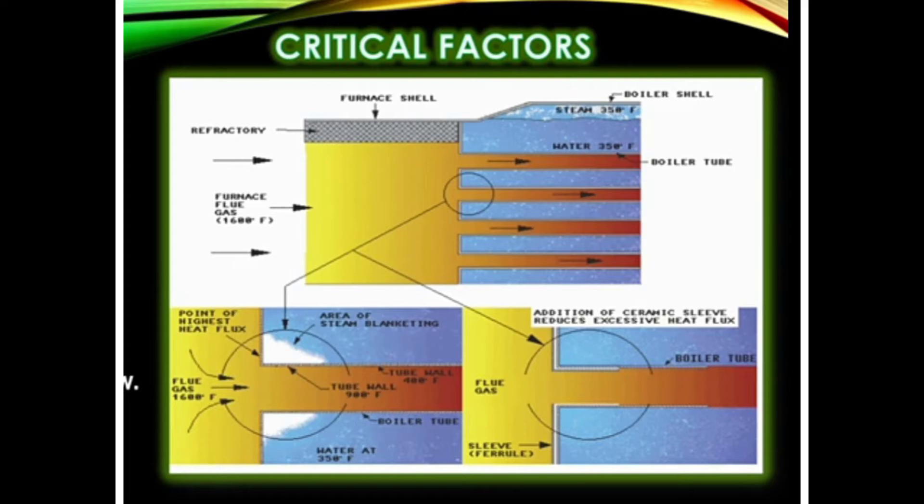At these corners or edges where flue gases first enter, there is very high heat flux and temperatures reach 900 Fahrenheit. Due to this high temperature, steam pockets are created at the corners, which is called steam blanketing. This ultimately causes overheating of the tube and leads to tube failure.